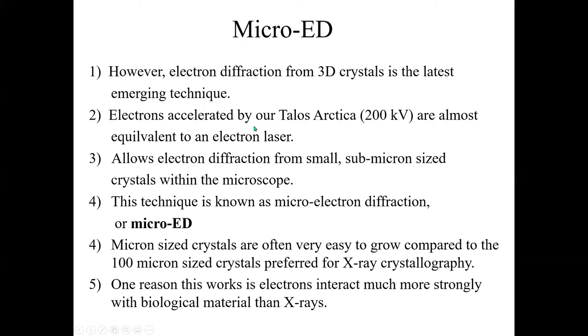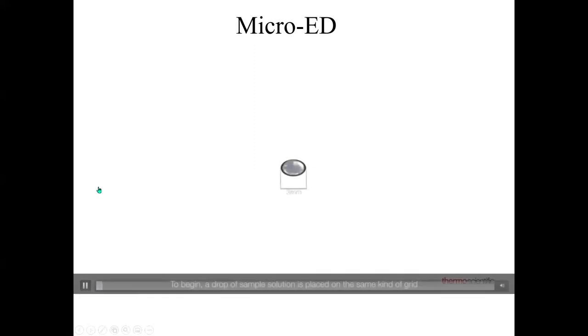MicroED will collect diffraction data from 3D crystals inside a microscope. When we accelerate electrons in the Talos Arctica, it's almost like a 3D free-electron laser that allows diffraction from very small, less than micron-sized crystals. These micron-sized protein crystals are often much easier to grow than the larger crystals needed for x-ray crystallography. Electrons also interact with biological materials much more strongly than x-rays, so scattering from small crystals is much stronger.